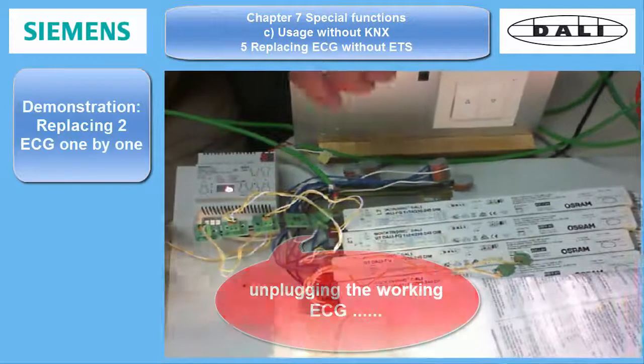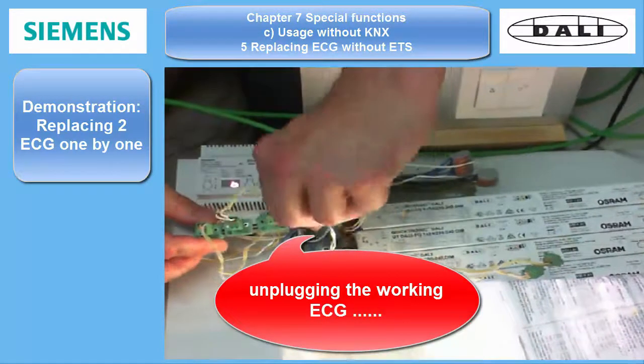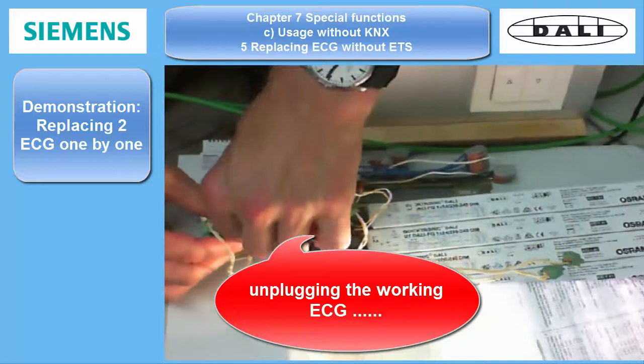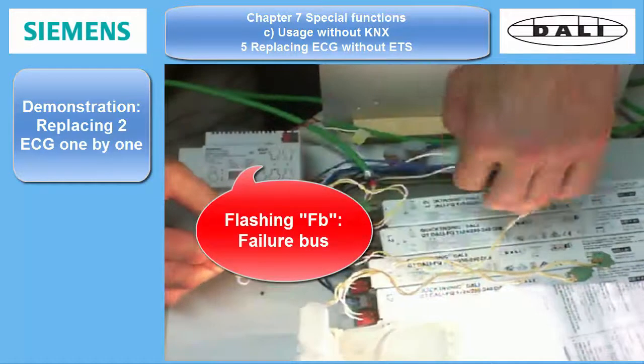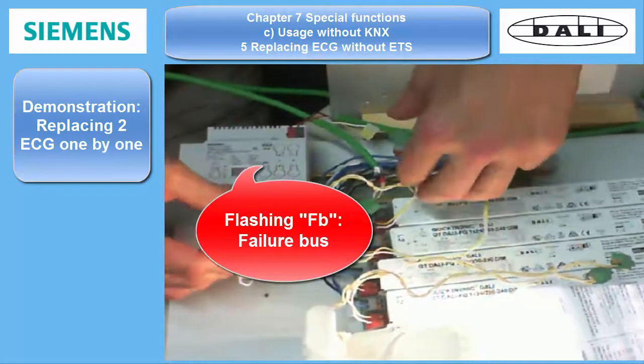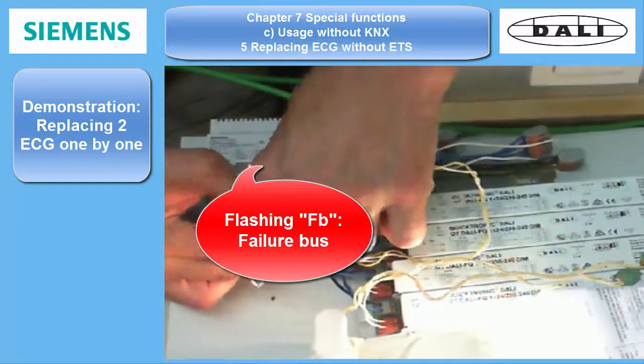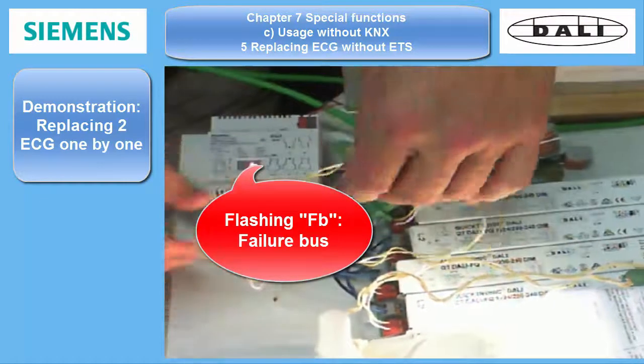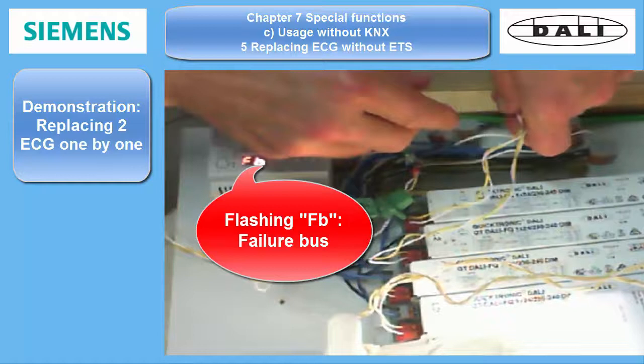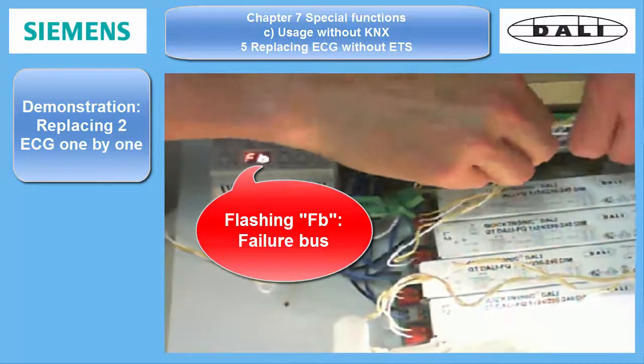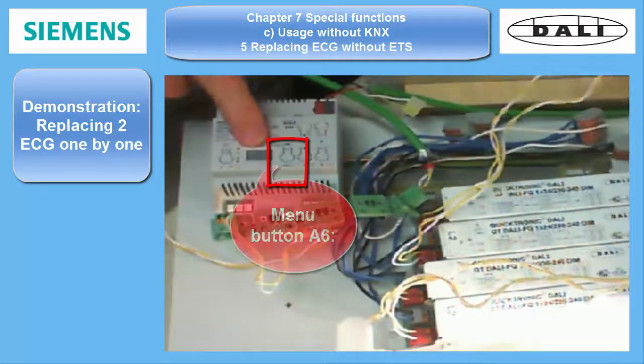Now I simulate the dropout of both ECG by unplugging them from the DALI bus. Watch the front side display of the DALI Gateway. From B, bus active, it turns to FB, failure bus, signalizing that something is wrong.